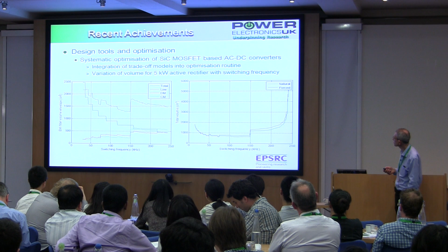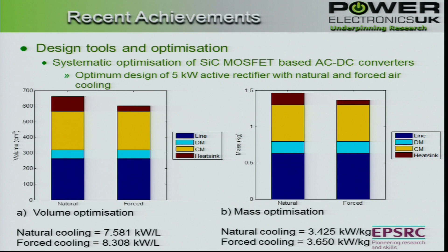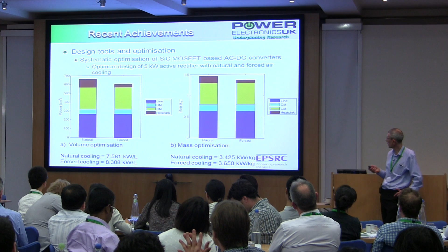These results show the power densities achievable, in kilowatts per litre and kilowatts per kilogram, based on the technology assumed in the models, with either natural convection or forced cooling of the heatsink. The best reported is a little less than 10 kilowatts per litre, with two-level circuits. The graph shown earlier illustrating reduced loss with multi-level circuits suggests these are likely to deliver much improved power densities, since losses will be lower and the heatsink smaller.